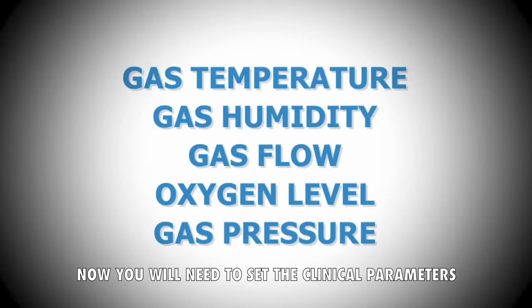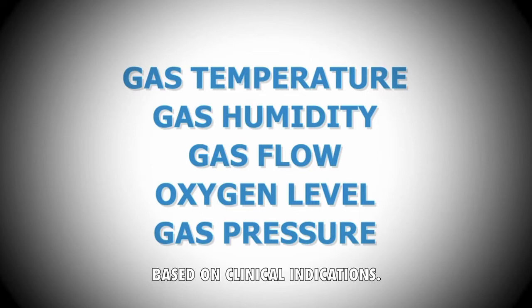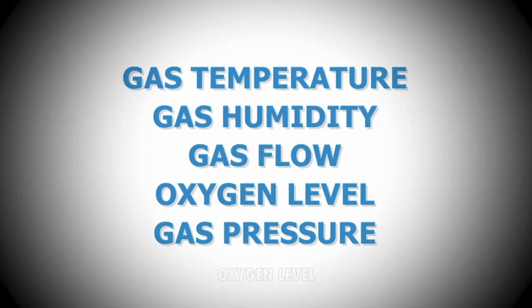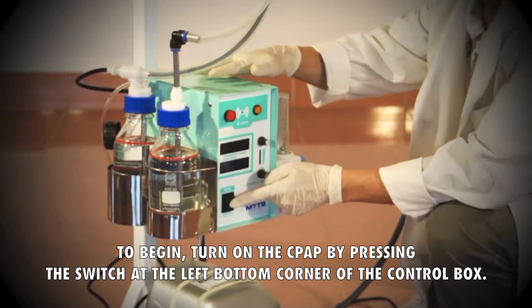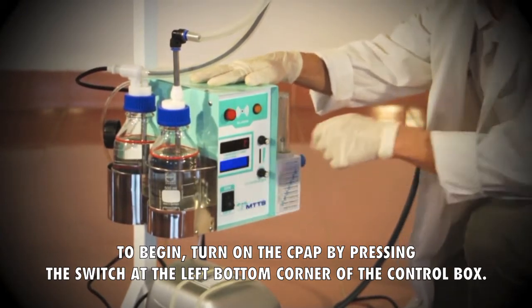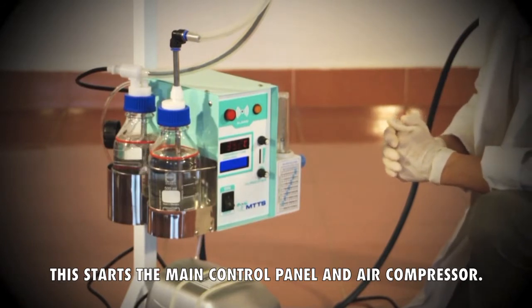Now you will need to set the clinical parameters based on clinical indications. These parameters are gas temperature, gas humidity, gas flow, oxygen level, and gas pressure. To begin, turn on the CPAP by pressing the switch at the left bottom corner of the control box. This starts the main control panel and air compressor.